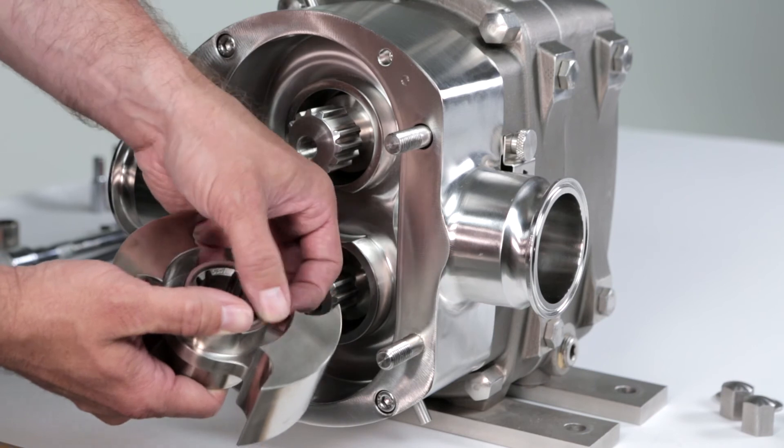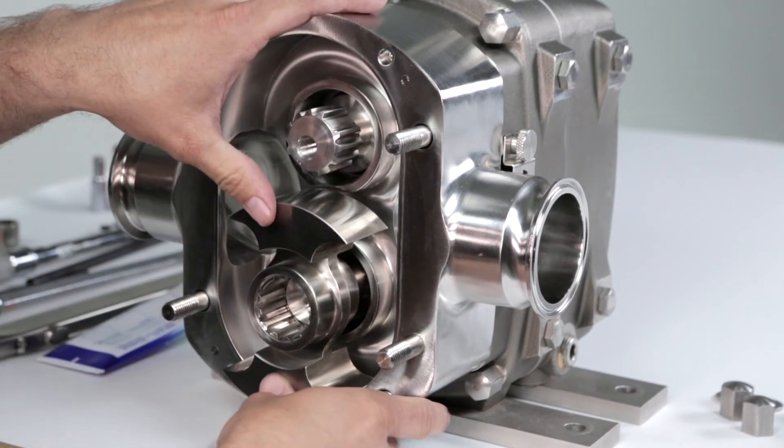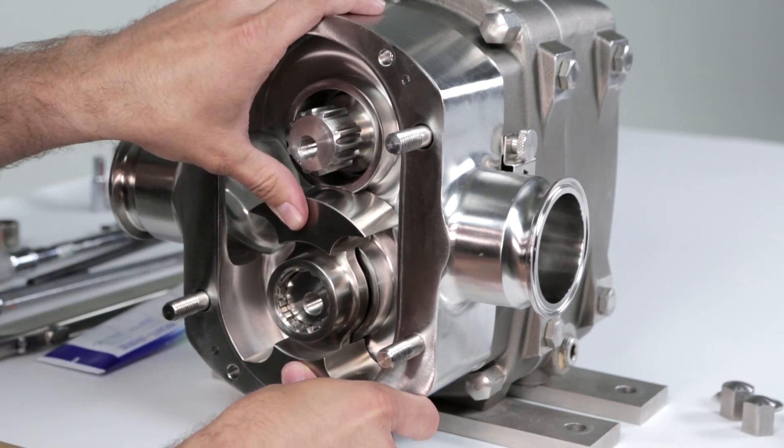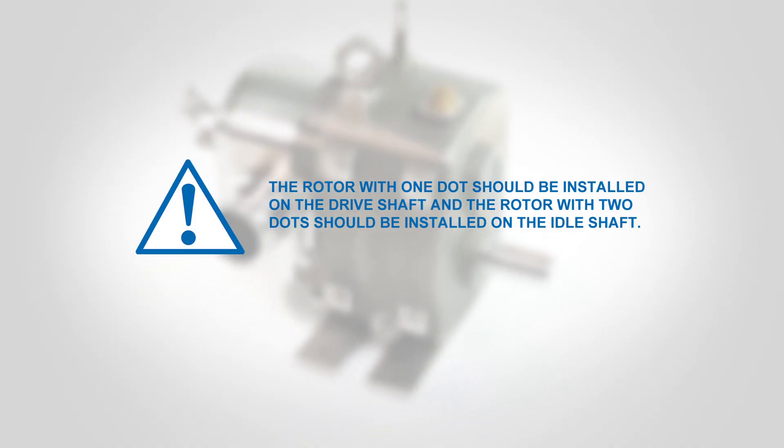Install the rotor o-ring on the back side of each rotor. Install the rotor with the rotor o-rings facing the back of the housing. Note, the rotor with one dot should be installed on the drive shaft and the rotor with two dots should be installed on the idle shaft.